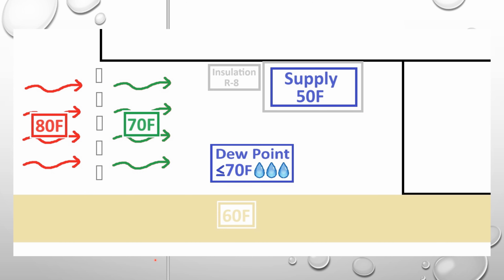So I go ahead and add my insulation, R8, around the supply duct, but I still haven't figured out what the outside temperature is, what is the temperature of the edge of this, because that's what's condensating. It's not inside the ductwork, it's on the outside of the ductwork. So what is that temperature? I'm going to show you a formula on the next slide on how I got there.